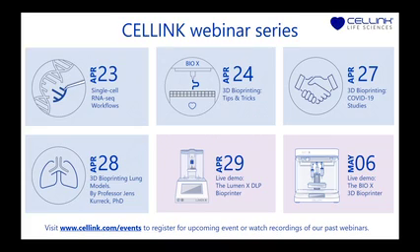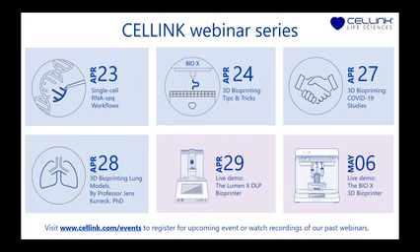Another question regarding cell detection: can the instrument detect irregular cell types or shapes? We use bright-field images along with fluorescent images to retrieve cell morphology, and we use parameters such as size, roundness, and fluorescent intensity to sort cells. So yes, we can also target cells that are for example elongated and sort only those into the plates, or target the ones that are round.